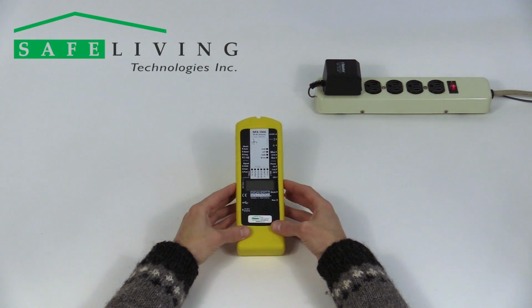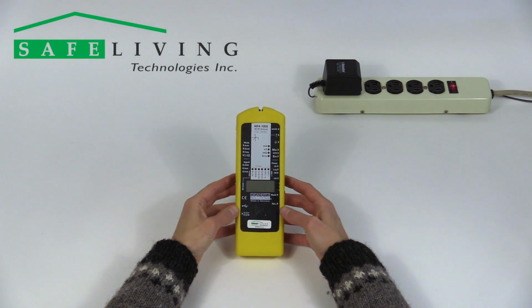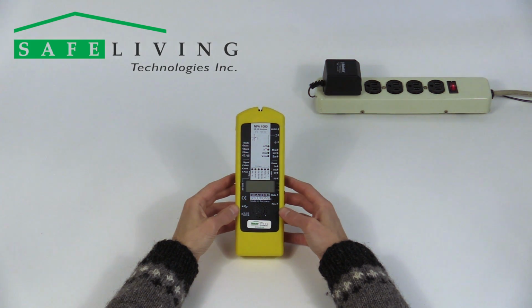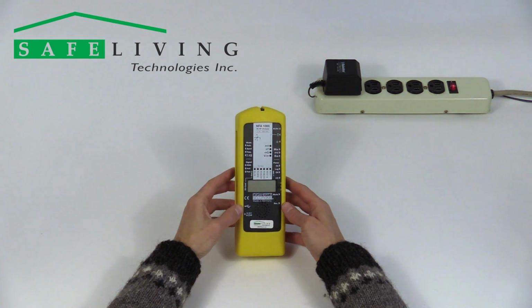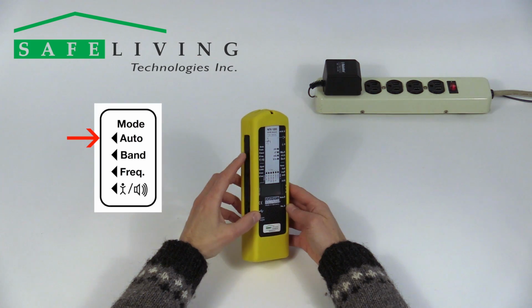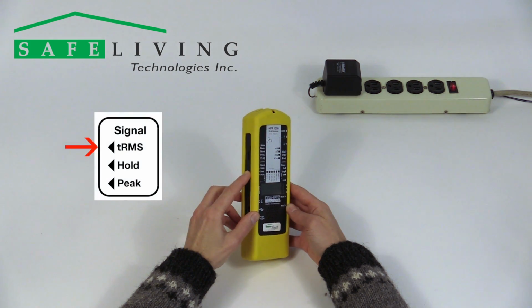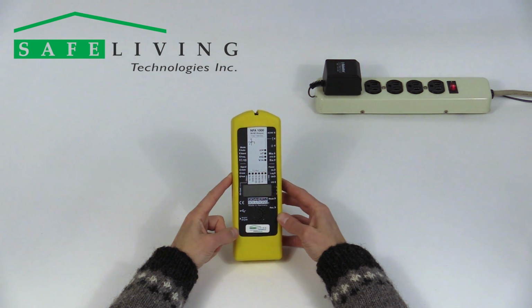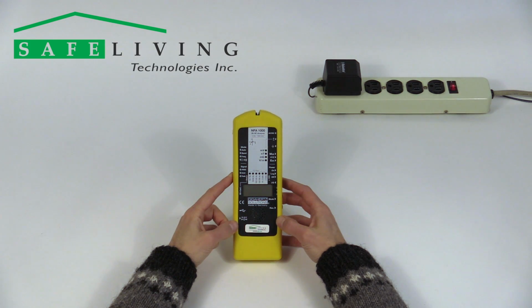For conventional measurement of AC magnetic fields, simply set all the switches to the up position. Shown here, the mode is set to auto and the signal is set to TRMS. True RMS is the default building biology and industry standard mode that should be used when measuring AC magnetic or electric fields.